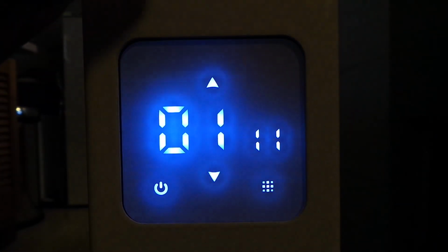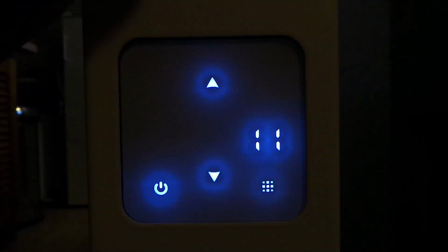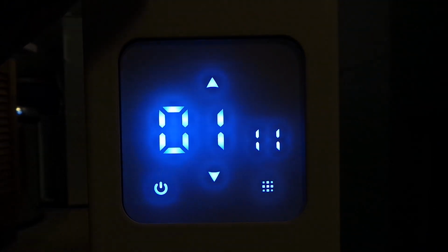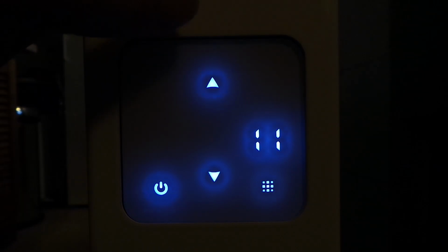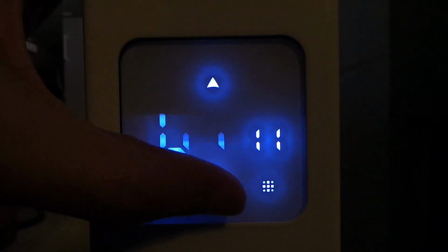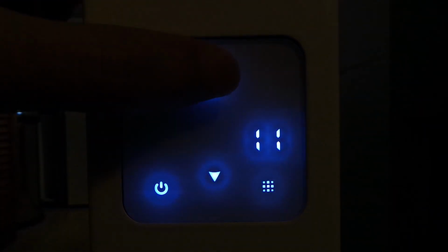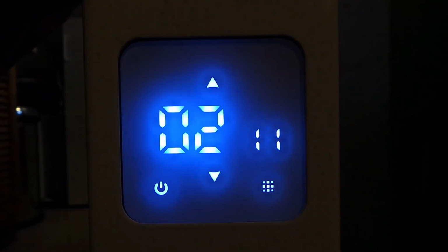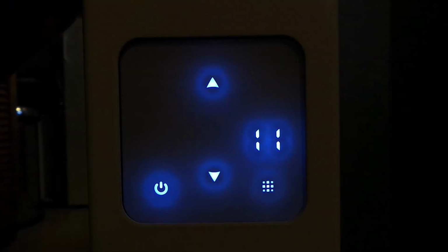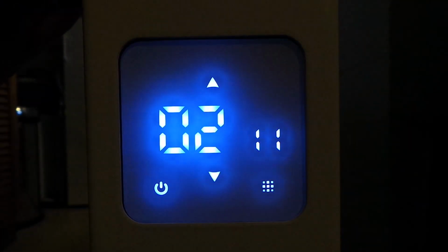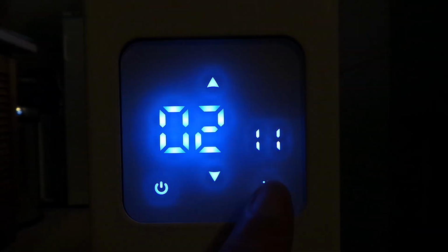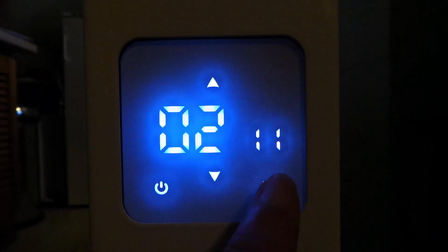If you have a value of 1, it allows the radiator to just have 1 day which is different, so 6 days will be the same. For example, if you work Monday through Saturday, you might want to set those days to be the same programming, and then Sunday, day 7, will be a different setting. If you use a value of 2 here, then all 7 days will be programmed the same. And that's the value that we're using here. We want all values the same. So I'm going to leave that in value 2, which is not the default state. That's 7 days programmed with the same times and temperatures.